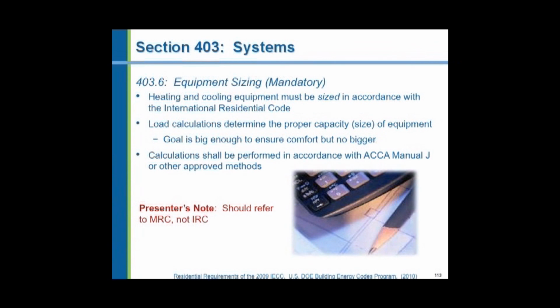Equipment must be sized in accordance with some kind of a calculation program. The heating and air conditioning equipment is required to be sized properly so that the building does not have an oversized furnace or an undersized air conditioner. And one example is ACCA Manual J, Air Conditioning Contractors of America Manual J, which is based on the ASHRAE methods for calculating heating and cooling loads.